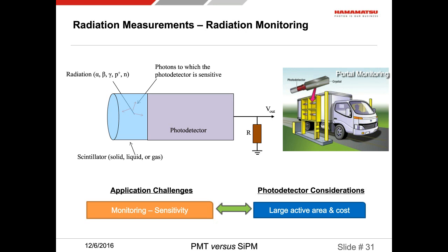In this case, we use a scintillator. What happens is that the radiation particle is absorbed by the scintillator, where its energy is converted to light that the photodetector can detect. The scintillator acts like a proxy, or like a converter of radiation's energy into energy in the form of light that the detector can detect.